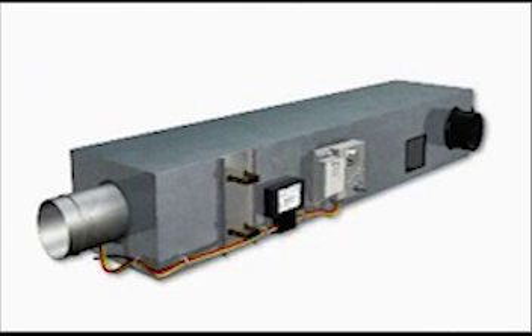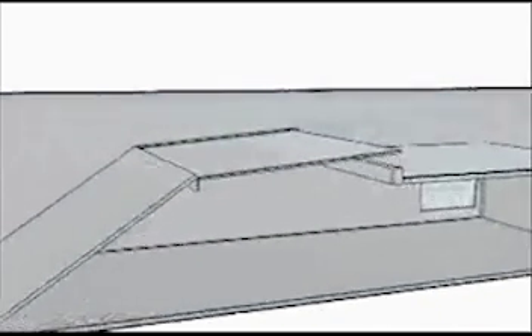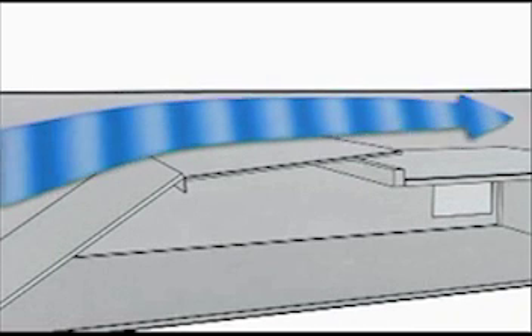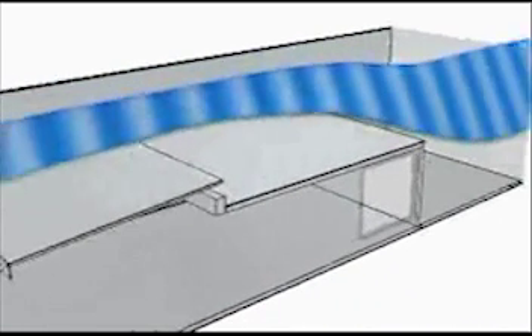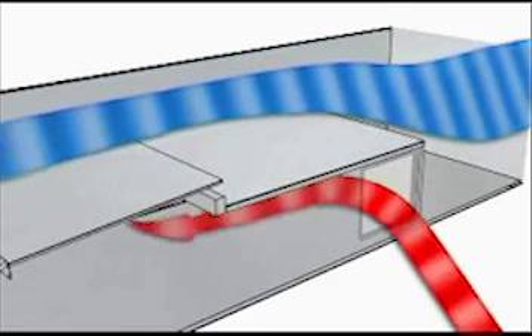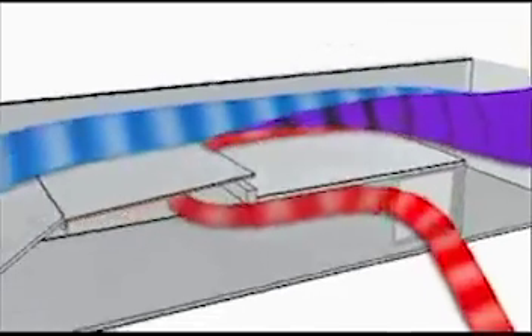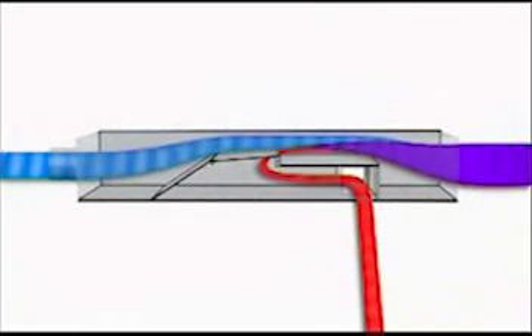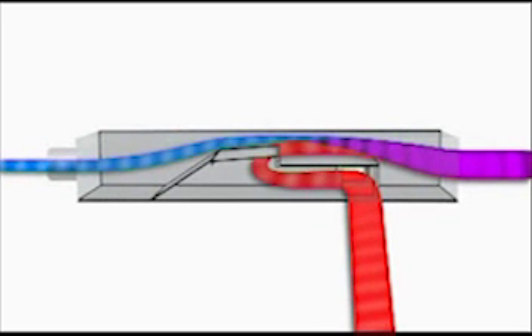As a solution to this problem, Barcol Air developed the induction VAV terminal. This sophisticated terminal ensures that in the minimum situation, proper air distribution in the room is maintained. The key concept of the induction VAV terminal is the jetronic damper. This damper controls the primary air volume, shown here in blue. At the same time, the damper creates a Venturi effect, which induces room air into the terminal, shown here in red. In the maximum situation, the induction is relatively low, while in the 20% situation, the induction is much higher. The result is that the total air volume remains sufficient to maintain proper air distribution in the room.